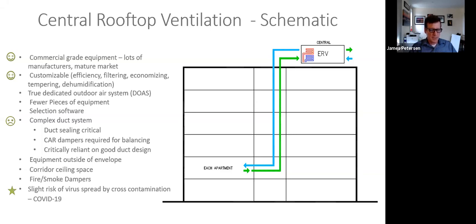Complex duct system is a major issue. Basically, it requires a retraining of everybody down the line to get the ductwork sealed, to get the ductwork balanced properly, and it's a major drawback and big hurdle to overcome to have a successful job. And then again, like the 4x4, it's going to have this inherent risk of cross-contamination at a very slight level, and when I say slight, it could be as low as 0.1% of total airflow, as high as 3%.